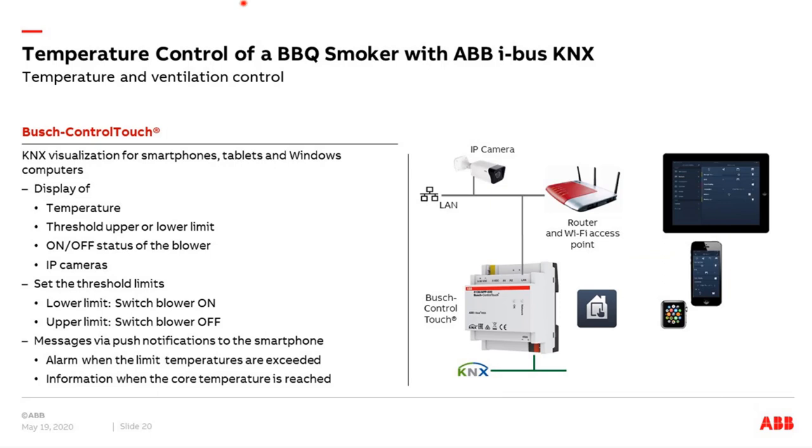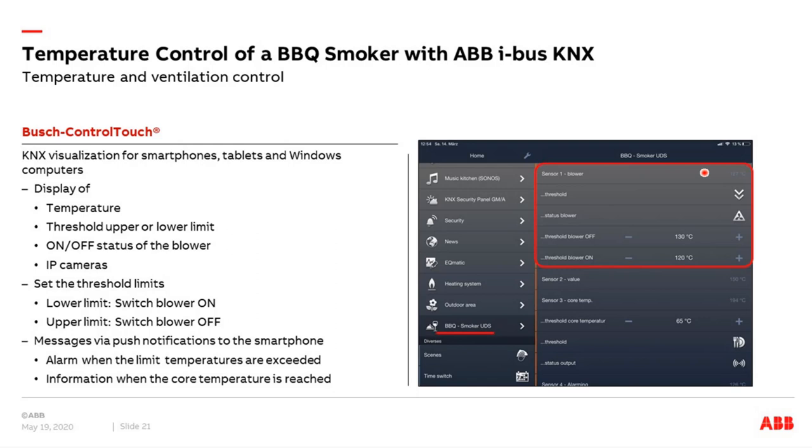For visualization of the complete UDS smoker — all values, or to change thresholds — I use the Busch-ControlTouch. The Busch-ControlTouch is connected to KNX and to the IP network, so I can also integrate ABB IP cameras. Communication to my smartphone and tablet is via Wi-Fi. On the display, you can see the temperature — for example, 127 degrees — measured via the PT1000 sensor. Then the threshold status: if it's below the threshold or has exceeded the upper limit. And the status of the blower — at the moment the blower is on. Via two buttons I can change the upper limit and lower limit using plus/minus, and the control touch sends the 2-byte values to the analog input to change the thresholds. Additional temperature sensors can also be viewed.